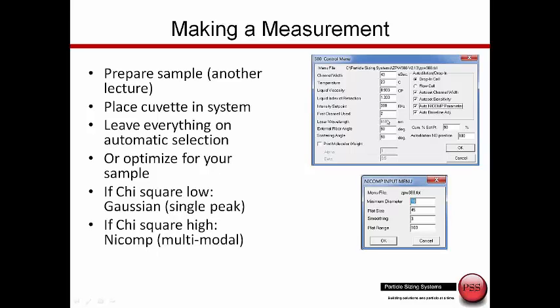A feature that is unique with NICOMP is an immediate presentation of a chi-square error calculation, which then indicates do we think there is a single peak or should we use the NICOMP algorithm to look for a multimodal result. This ability to do multimodal analysis is one of the key strengths of the NICOMP DLS system.